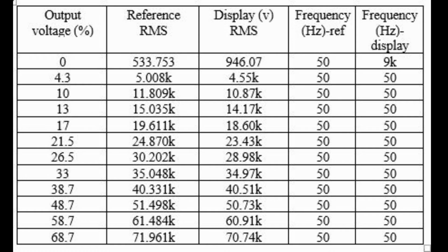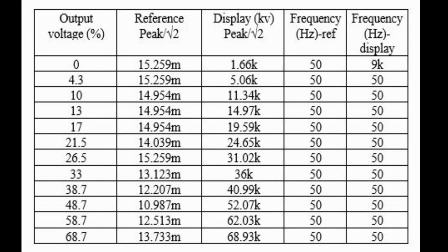So, the output voltage we can calibrate in percentage, that is from 0 to 68.7. The first table shows the reference RMS and the display RMS, with the nominal frequency set to 50 Hertz. The second table has the reference peak over square root 2 value and the display peak over square root 2 value, and the frequency is likewise set to 50 Hertz. Actually both values can be obtained on the same screen, but I have put them in different tables.